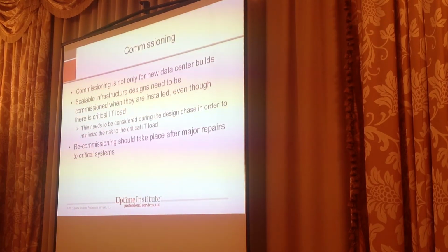It's not only for new data centers. Like we talked about a minute ago, when you start adding capacity components, two or three more generators, you need to commission those individual generators and then commission them as a totally integrated system. So anytime you have major installs or even major repairs, you should do commissioning.